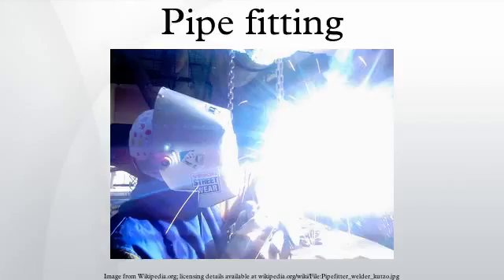Rigid copper. Rigid copper is a popular choice for water lines. It is joined using a sweat, compression or crimp-pressed connection. Rigid copper, rigid due to the work hardening of the drawing process, cannot be bent and must use elbow fittings to go around corners or around obstacles.